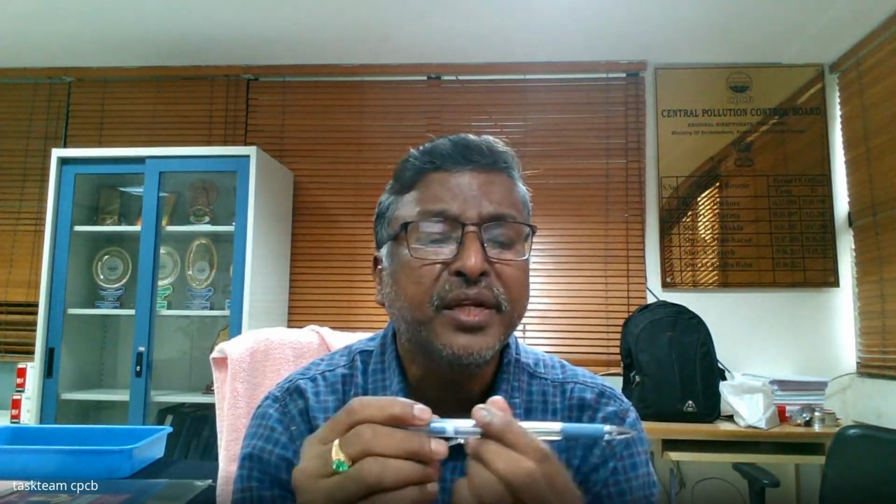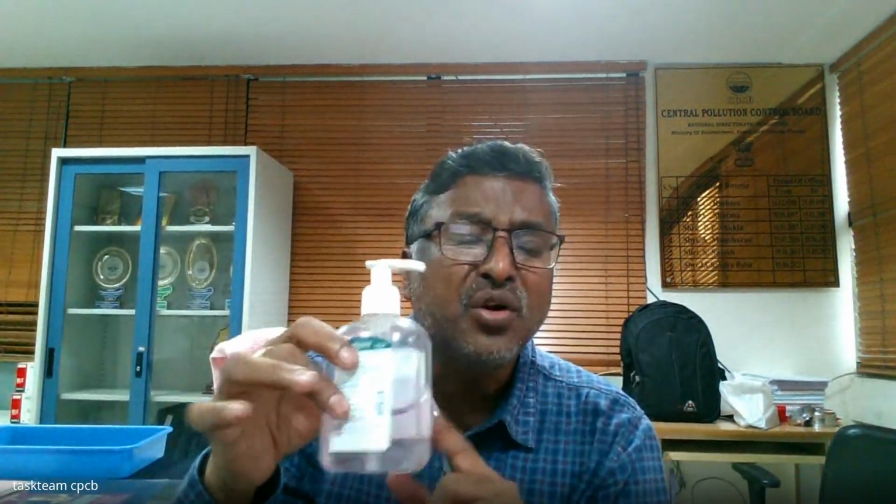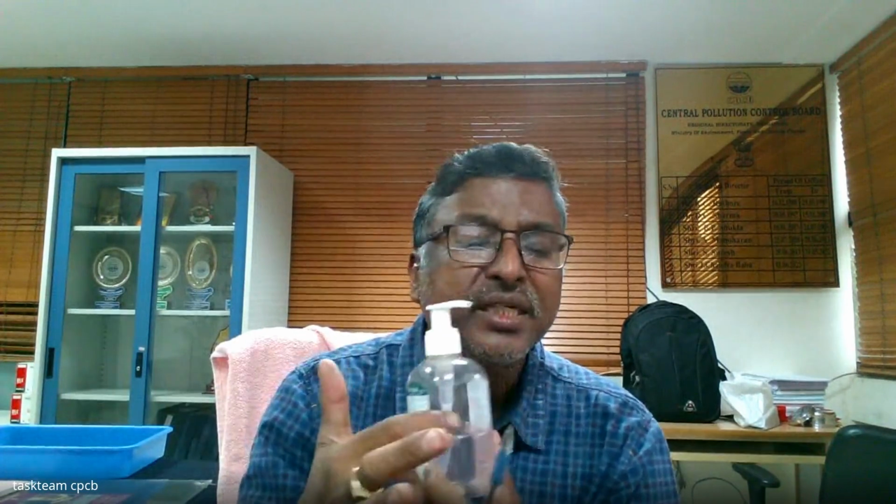Then we have got contaminated mercury-bearing material. One is the syringe, a contaminated mercury syringe. It has some residual mercury. When you are cleaning, that area also may contain some mercury. Therefore, this will fall under the category of hazardous waste. Whatever mercury you have collected into this plastic bottle, half filled with water, you have to put a label stating hazardous waste. You have to keep this in cold condition so that it is not going to evaporate.